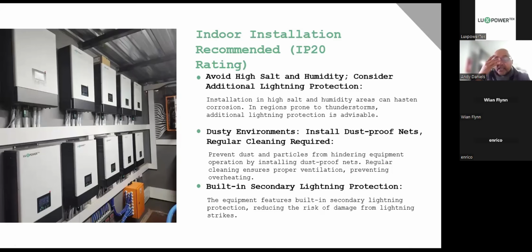It certainly increases the ventilation through the machine. But those foam filters are critical for keeping dust particles out of the inside of the machine, right? If you are in a particularly dusty environment, I've seen machines installed in workshops where the guys are either spray painting, or we've had a very interesting one where the guy was doing woodworking in his garage.